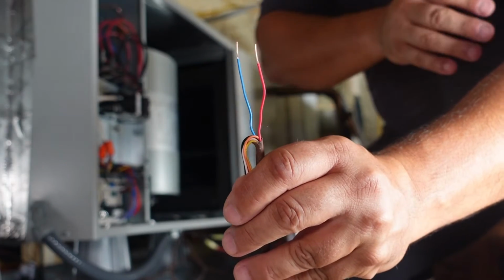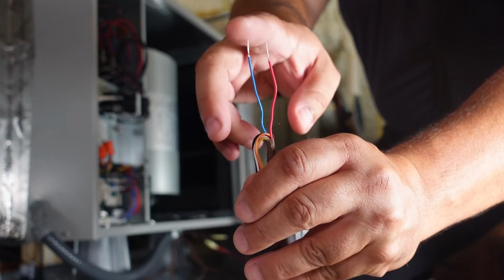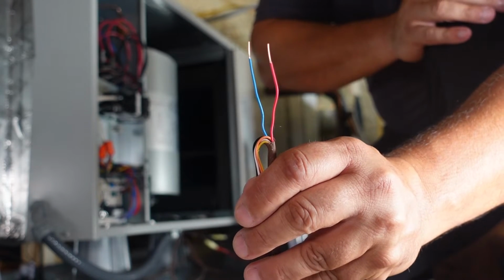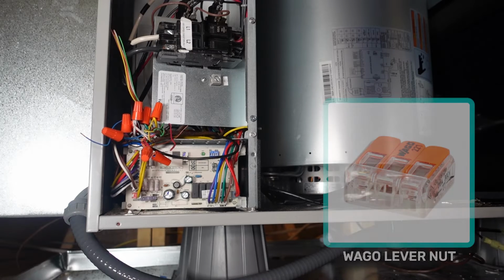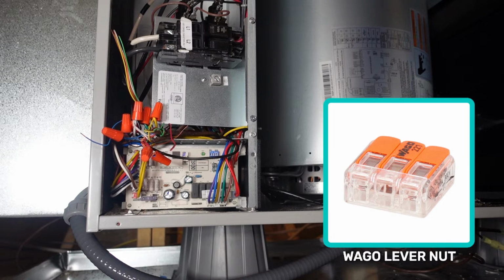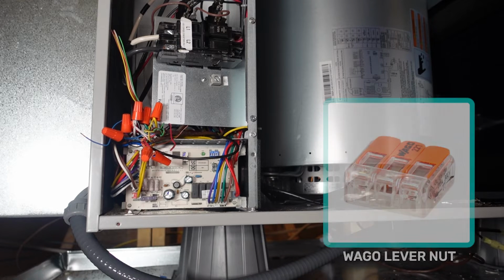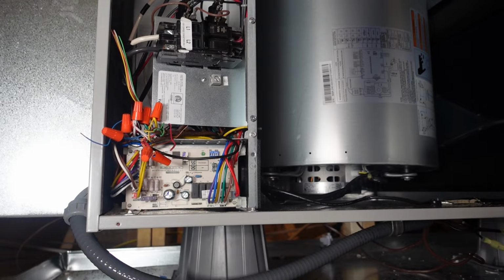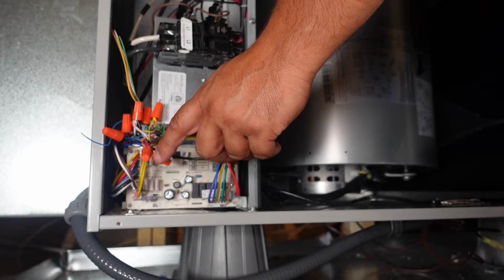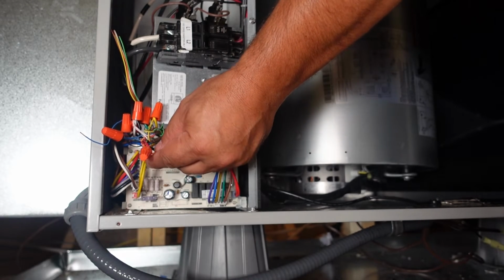Now strip out 2 inches from the cable jacket and 1 inch of wire insulation to prep the connection to the power source. Here you can use either the Wago lever nuts and splice the monitor power cable into the 24-volt transformer low side, or if you're planning to use the R and C terminals for power, you can directly connect the terminals like you would a thermostat.